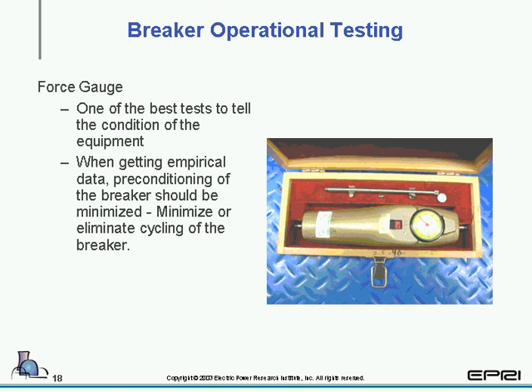And one comment on this, and we mentioned this several times in session 1, this is specific to breaker models. In other words, you have to review your own instruction manuals, the manuals from your vendor, to determine if there is any type of force gauge measurement. There may or may not be. It just depends on the breaker model and so forth.